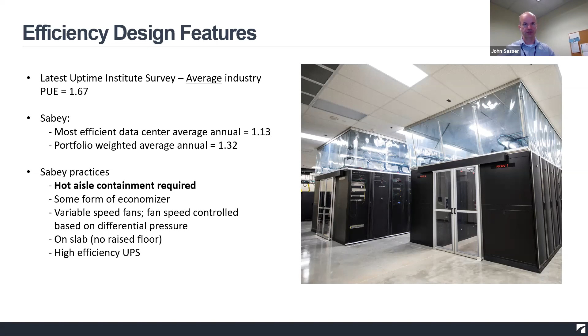Airflow management is very important. We use hot aisle containment, but it's not just about the containment you build around the servers, whether that's a chimney cabinet or a pod. You also have to manage the cabinets themselves, and as with a lot of efficiency measures, that involves interaction with the users—in our case, the customers who are loading and selecting the IT equipment.